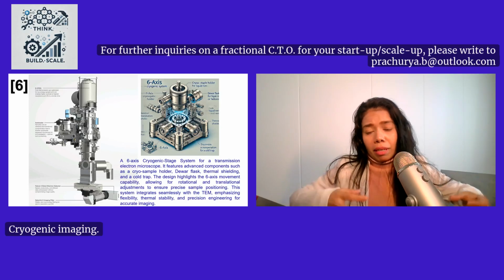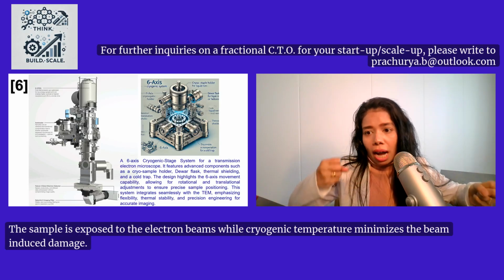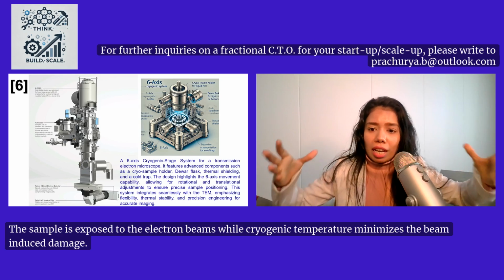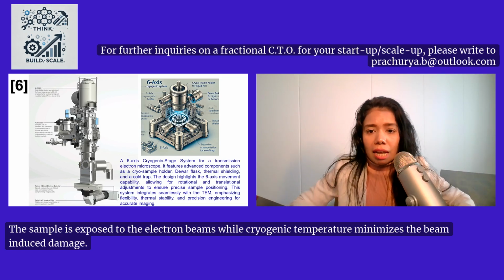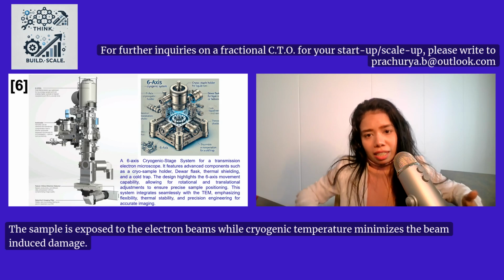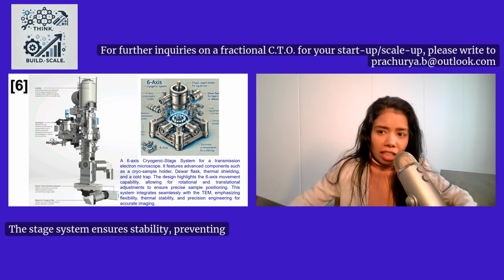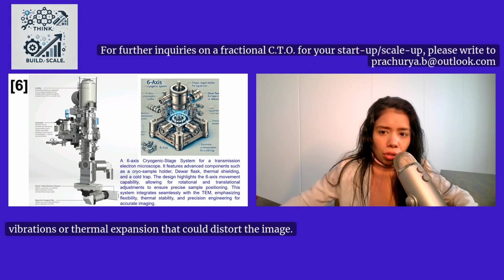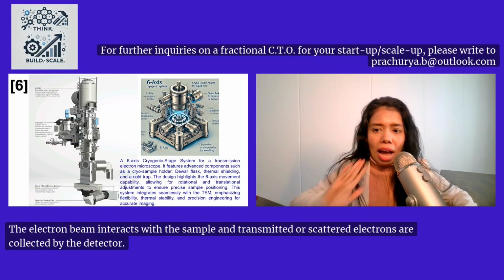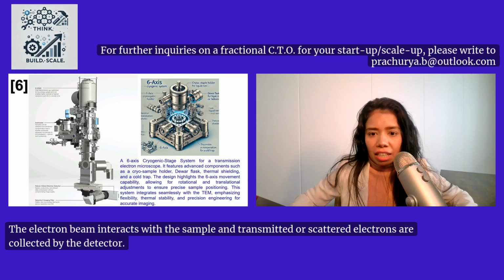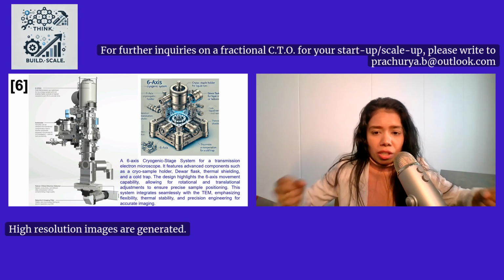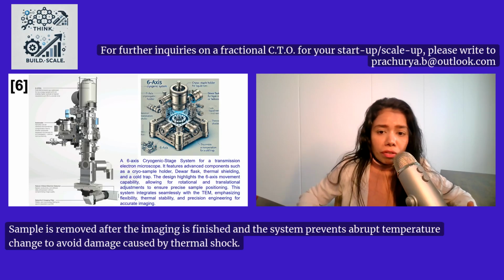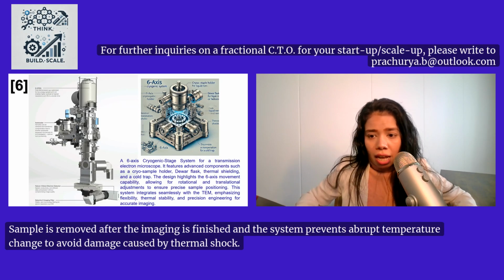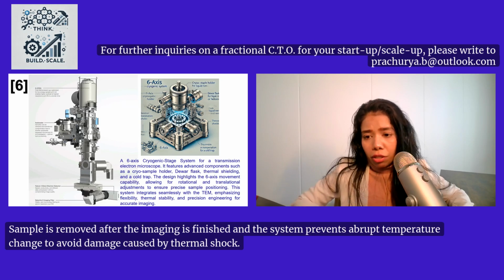Cryogenic imaging. The sample is exposed to the electron beams while its cryogenic temperature minimizes the beam-induced damage. The stage system ensures stability, preventing vibrations or thermal expansion that could distort the image. The electron beam interacts with the sample, and transmitted or scattered electrons are collected by the detector. High-resolution images are generated. Sample is removed after the imaging is finished, and the system prevents abrupt temperature change to avoid damage caused by thermal shock.